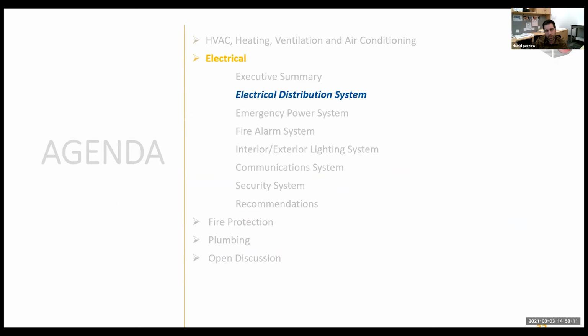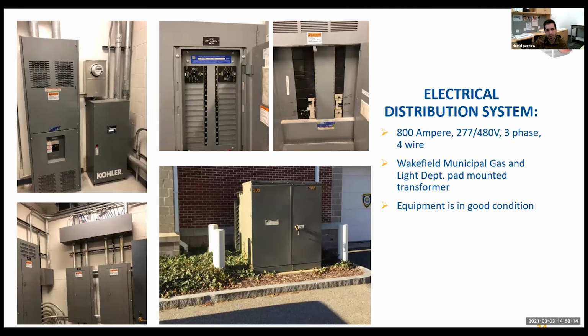Next slide. Here's some specifics on the distribution system. You can see the 800 amp board, and there's the picture of that transformer - you can see the close proximity to the Sally port, so that's something that needs to be considered. Generally National Grid and Eversource - I know this is a municipal light plant, but their requirements are likely the same - require 5 feet from a non-combustible wall, so that needs to be considered. I took some pictures of the distribution boards, and there seems to be adequate space to add sub panels and branch circuits to serve the areas being renovated.